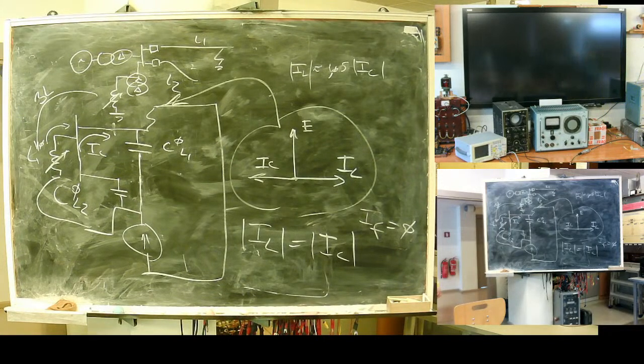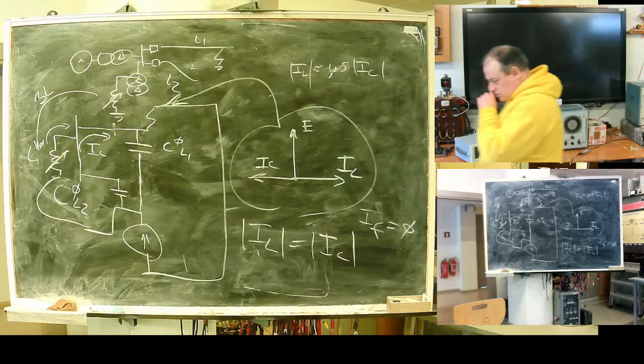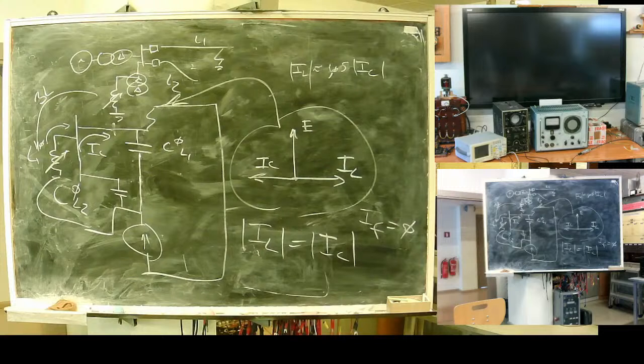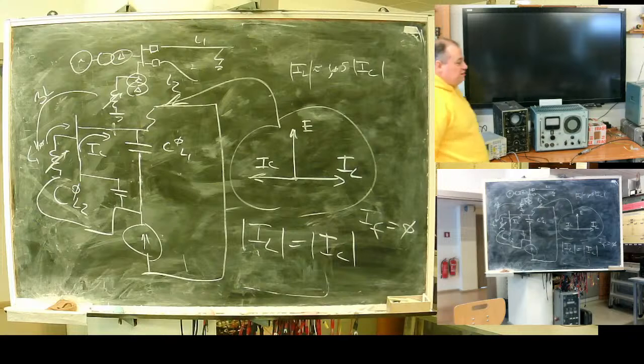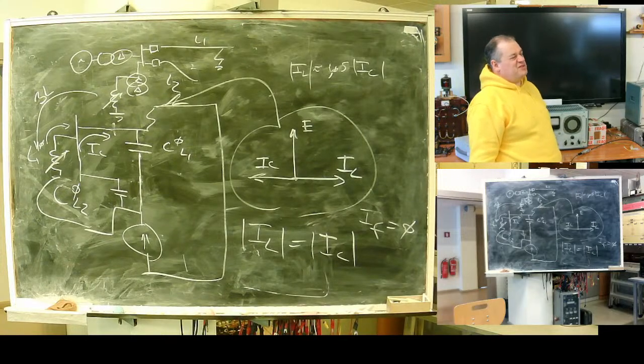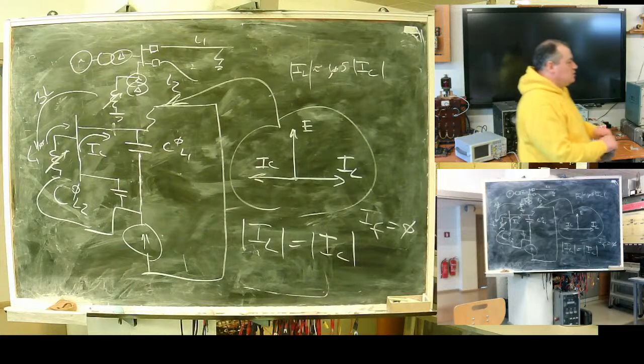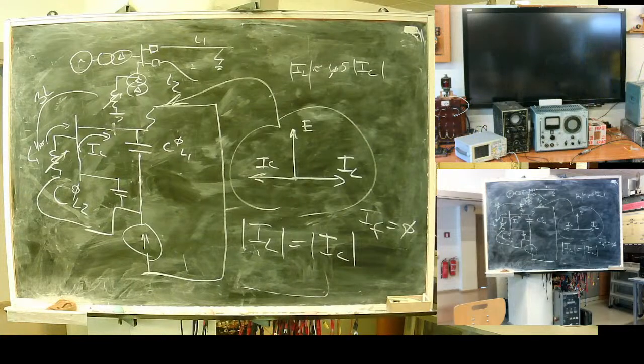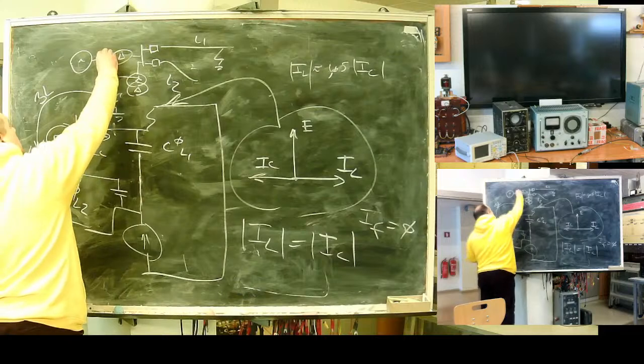But where's the problem? Problem, your protection will have no current. In case of compensated neutral, here our local rules require to install Petersen coil if earth fault current is greater than 15 amps. It was required to install this Petersen coil. In all, not modern one. Modern one are more complex.